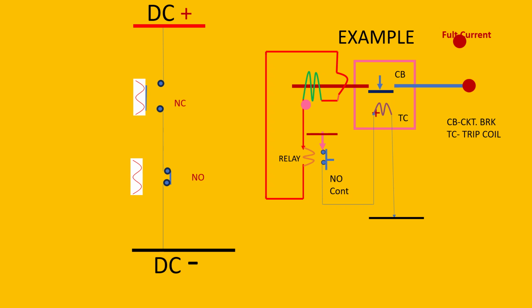But when a fault occurs, the CT secondary, also shown in green color, will pass current through the relay, and the relay setting, due to this fault, will attract the normally open contact. The relay coil will be energized and bridge the two normally open contacts, and DC positive will be extended to the trip coil of the circuit breaker, where one end is positive and the other end is permanently given negative of the CB trip coil.